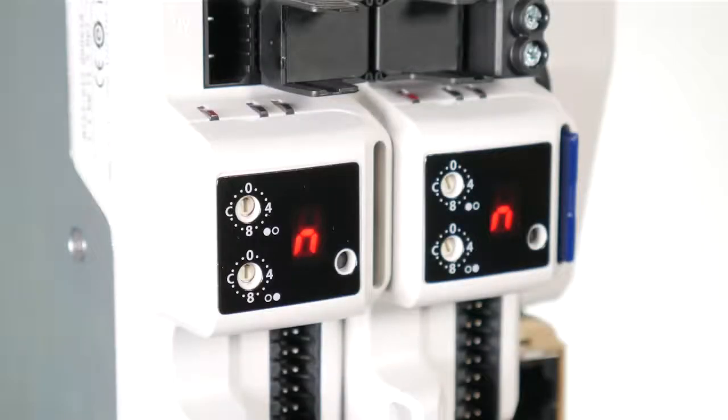The drive can be identified with a unique EtherCAT station alias or node address configured via the dials on the front of the KI compact display. The station alias or node address setting configured using the KI compact display is an 8-bit value or decimal 1 to 255.